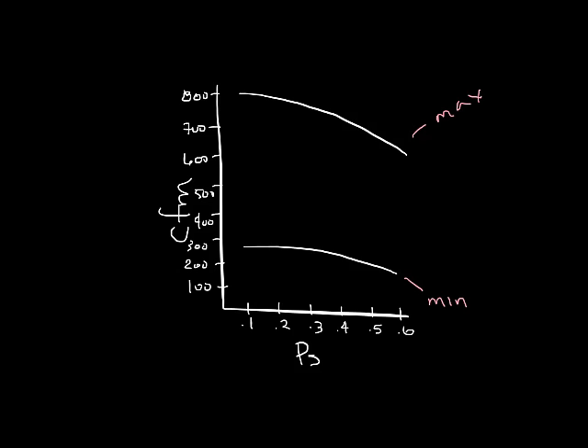Let's look at the maximum line. So if you look at a point up here at 0.2 inches of pressure you have just under 800 CFM. We'll call it 790. But at 0.6 inches of pressure you have closer to 600 CFM. So you can see when the pressure increases the airflow from the fan box decreases.